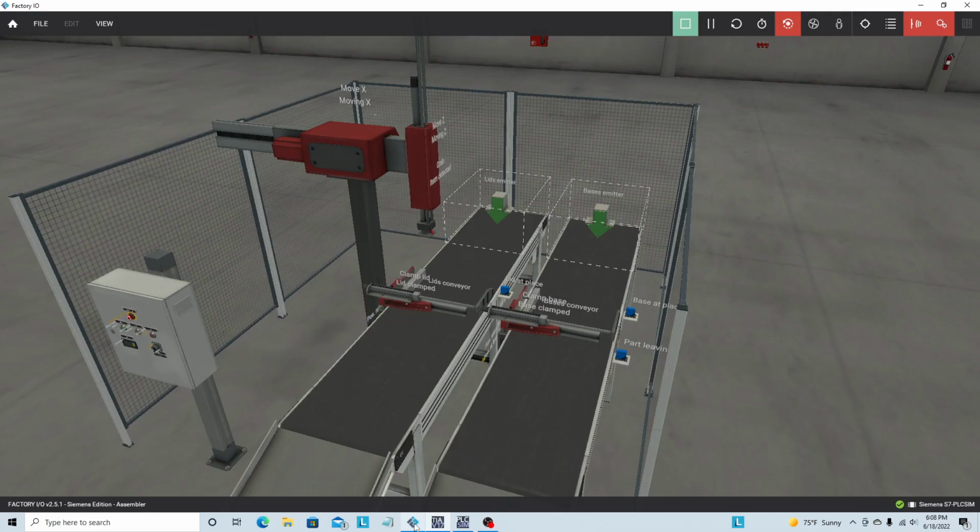something that we run into on this machine is that there's not a feedback for a work position or a home position, and we're using the movement, or the outputs with edges and one area of feedback. It's real easy, on the initial startup of the PLC, we won't have position.